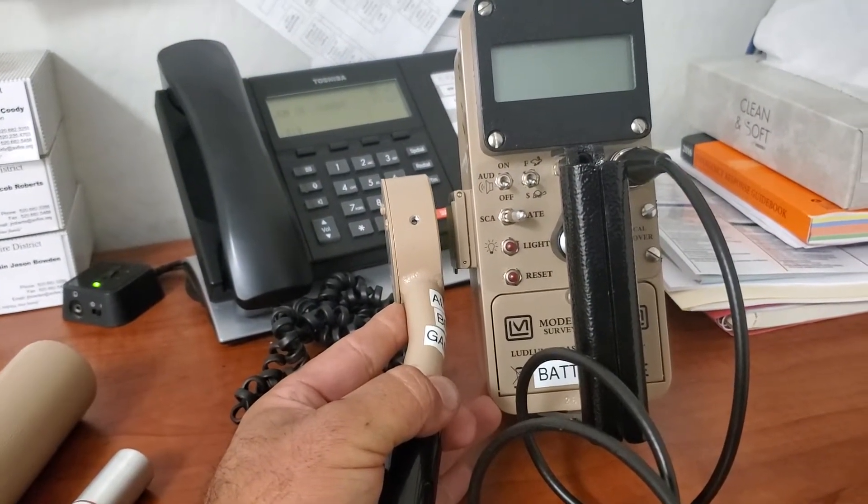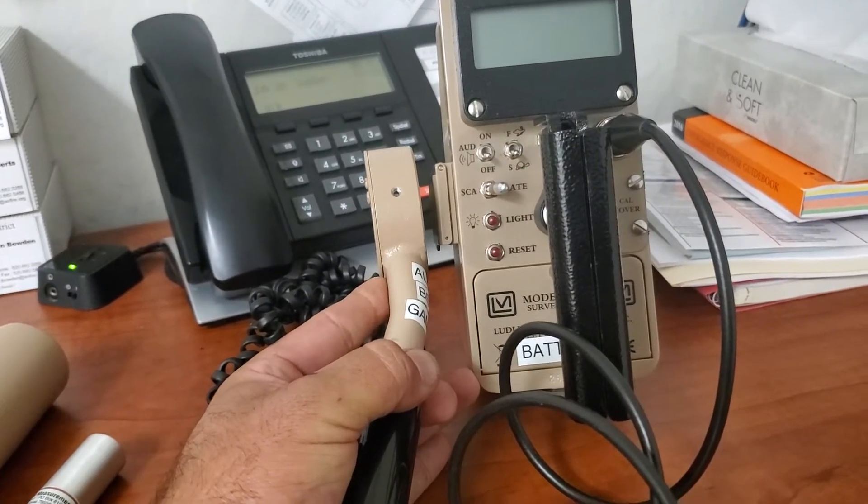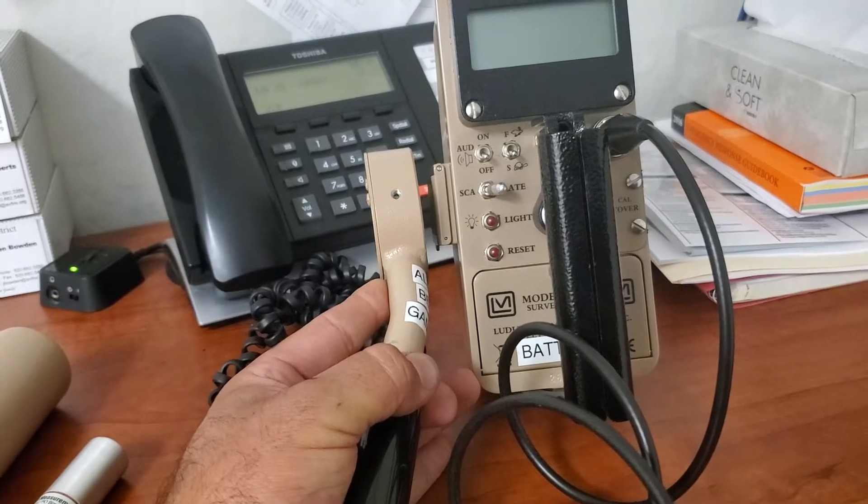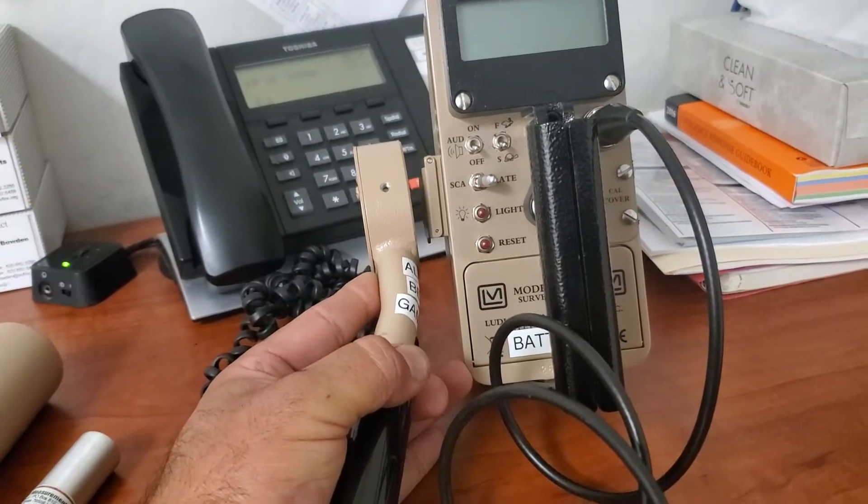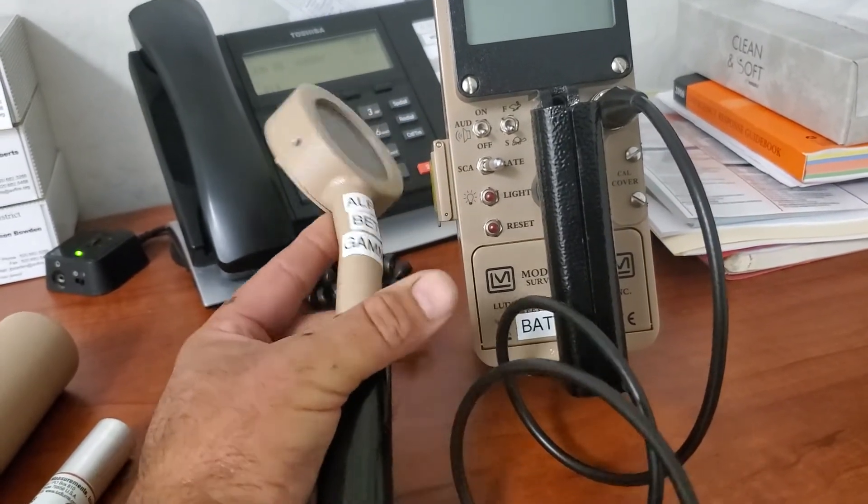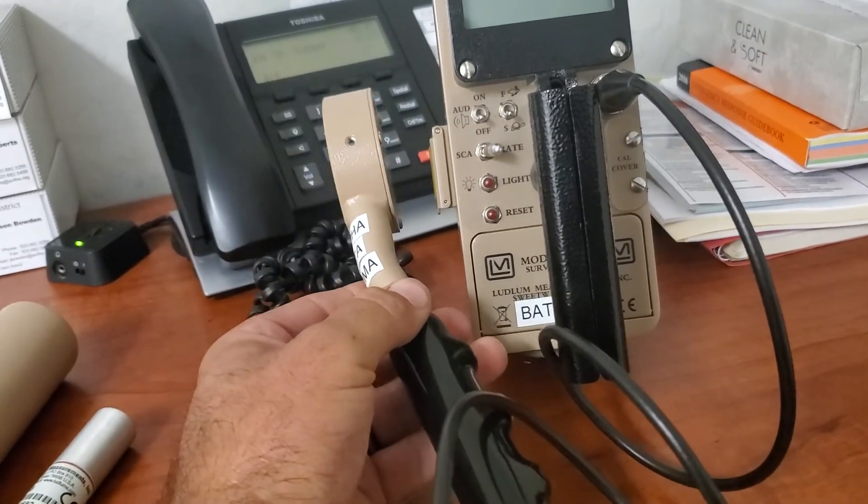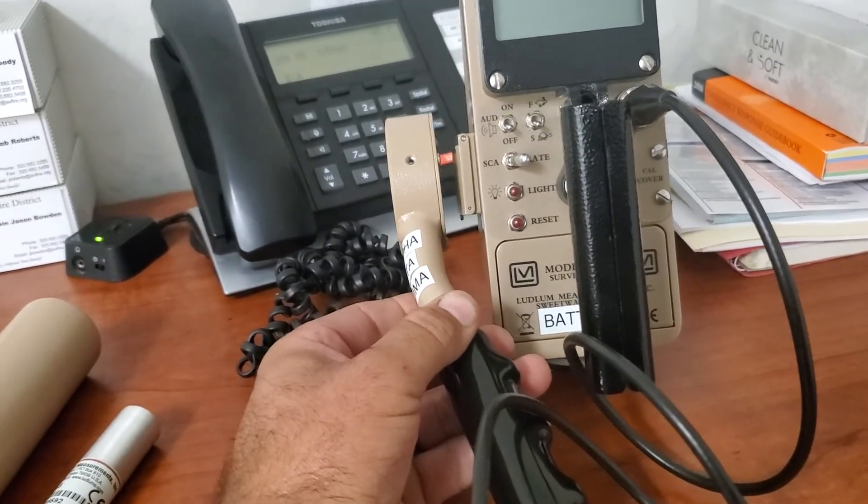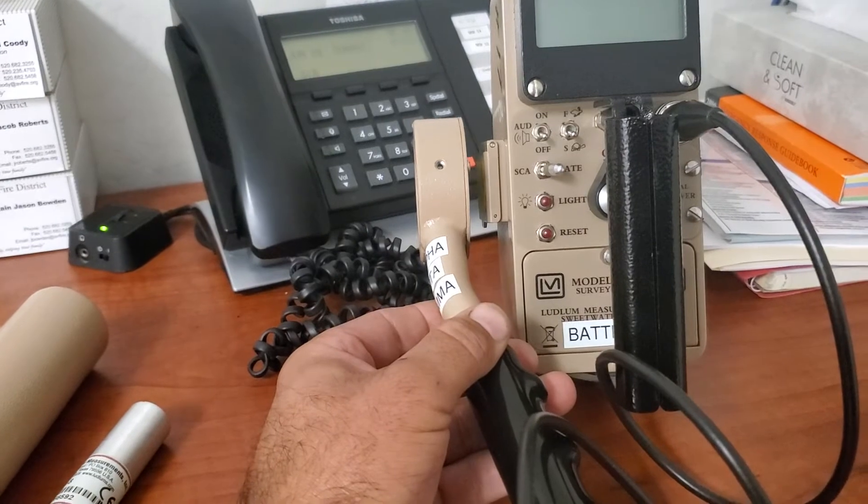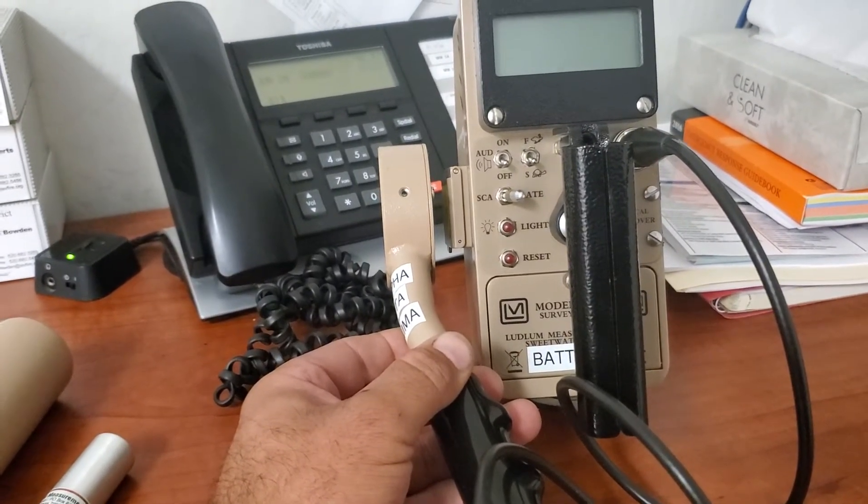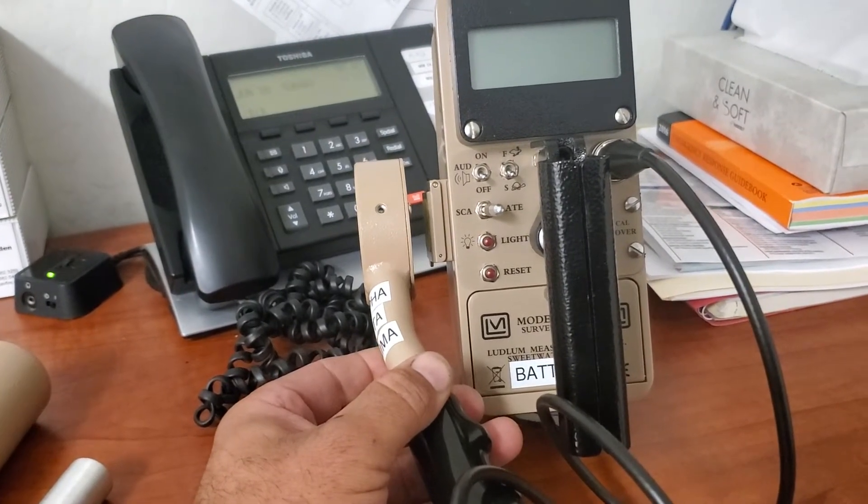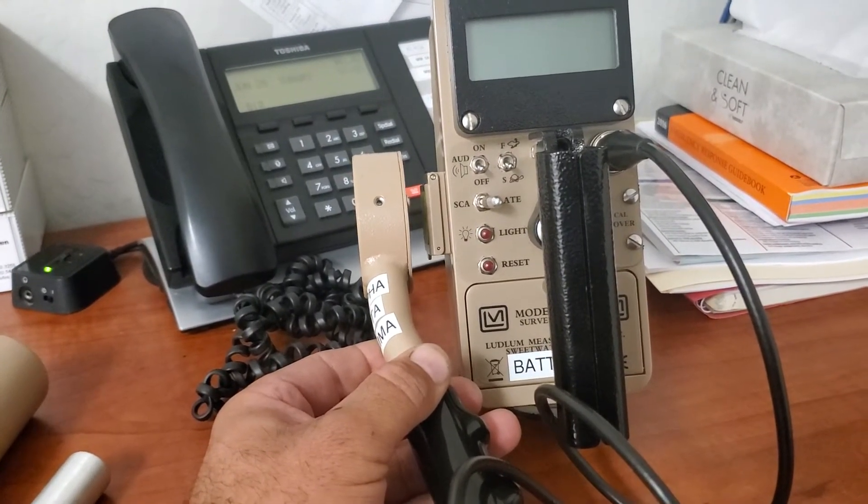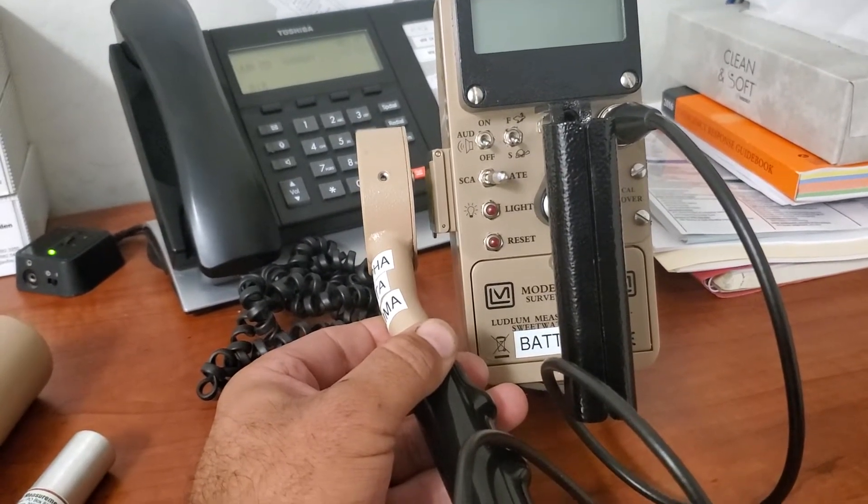One way to detect alpha radiation would be to hold that probe within that one to two inches for that alpha range and get your hits. This probe is going to read anything at this range right now. If you wanted to eliminate the alpha, you could either move away farther than one to two inches, or the trick of the trade is you flip this over and the metal backing plate on this should be enough to block any of the alpha emitters coming off of that source, which would eliminate the alpha, which would leave you only with maybe some really strong beta or definitely gamma radiation. Gamma radiation would go through the back of this with no problem.